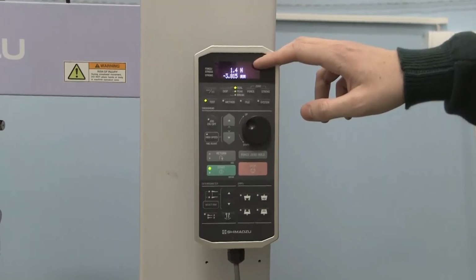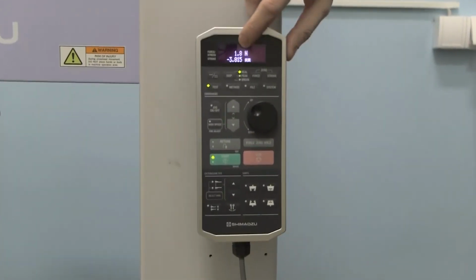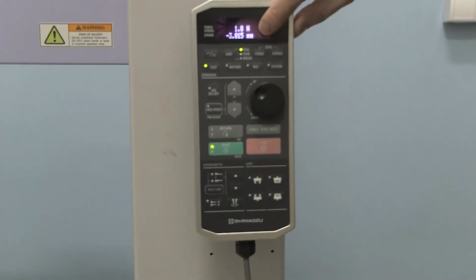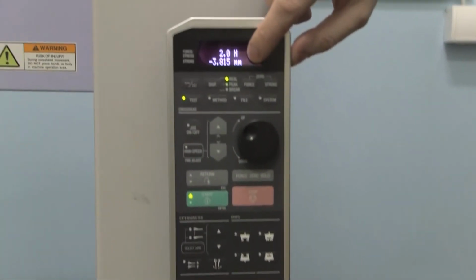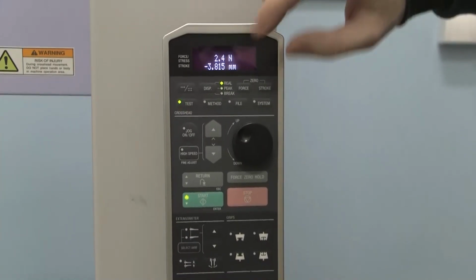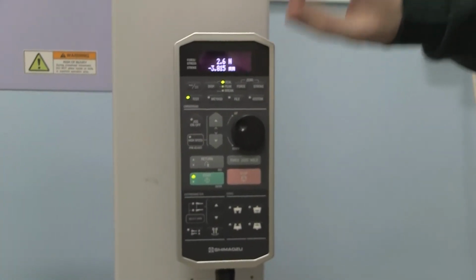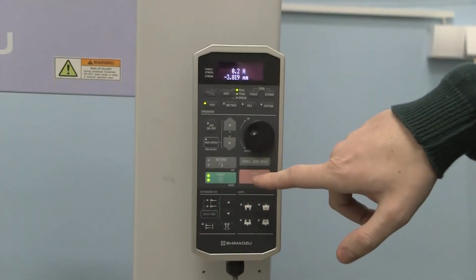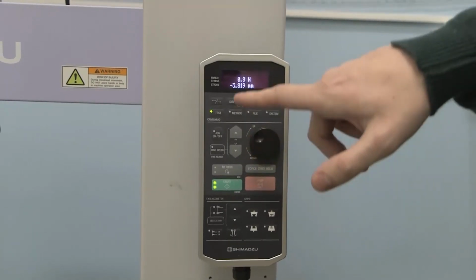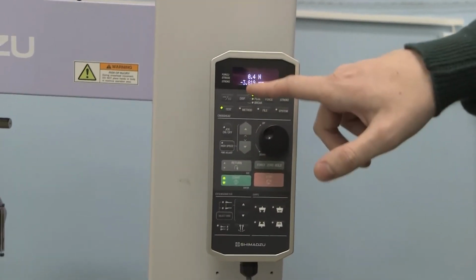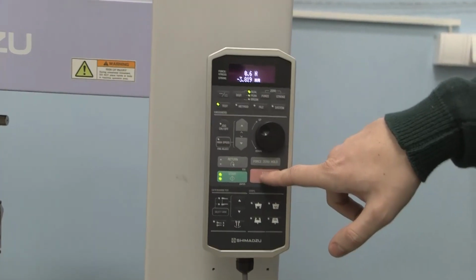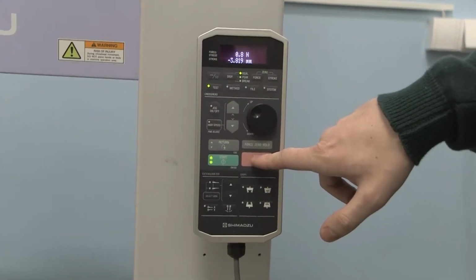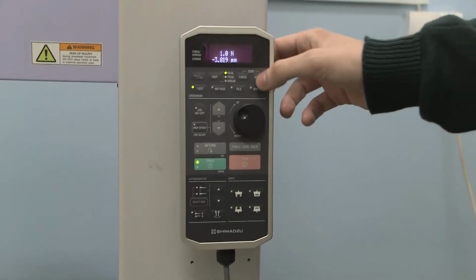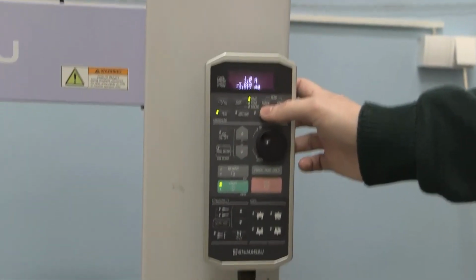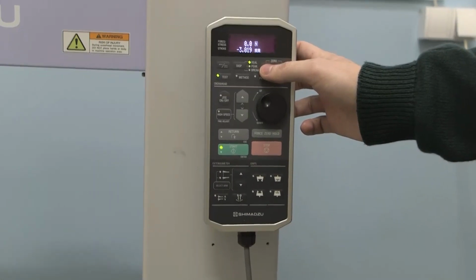After inserting the specimen, we have a reading of about 2 newtons of force, and we have a minus value of displacement. What we need at the first period of the testing is to set all the values to 0. So for the force, I'm using force 0 hold to have it as close as possible to 0. I'm stopping the force 0 hold option now, and now we have about 1 newton of force. So using the 0 force option, I'm zeroing the force.